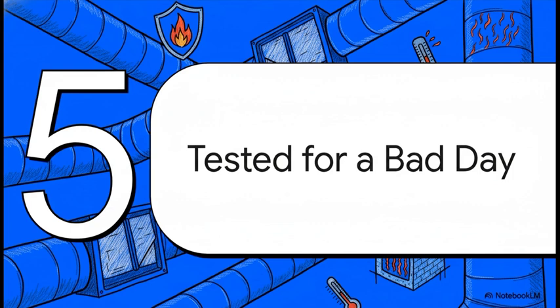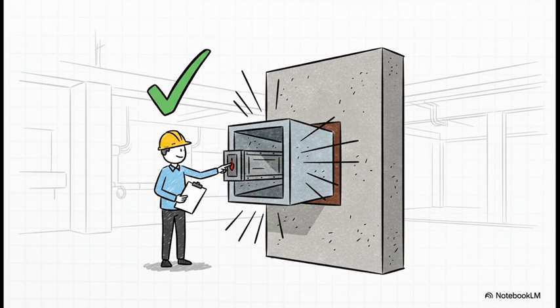Now, having all this gear is great, but how do we know it's actually going to work on what could be the worst day of that building's life? This is crucial — none of this is left to chance. Chapter 7 of the standard requires that before anyone even moves into the building, every single one of these dampers gets tested. An inspector physically triggers them to make sure they close just like they're supposed to. This isn't just an installation, it's a verified life safety system.